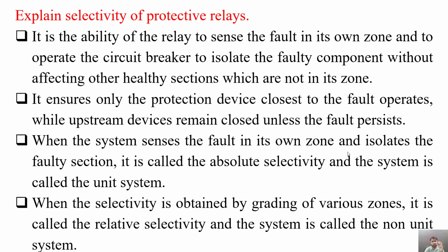So first of all, the definition of a selectivity property is it is the ability of the relay to sense the fault in its own zone and to operate the circuit breaker to isolate the faulty component without affecting other healthy sections which are not in its own zone.